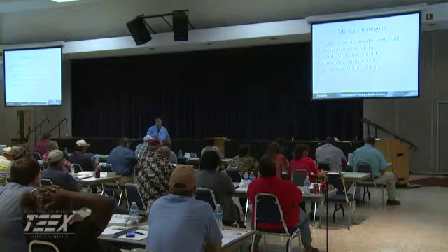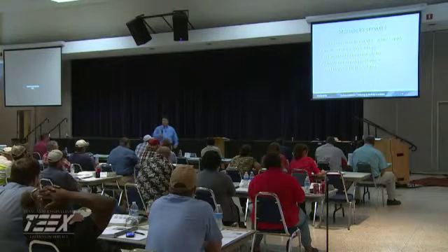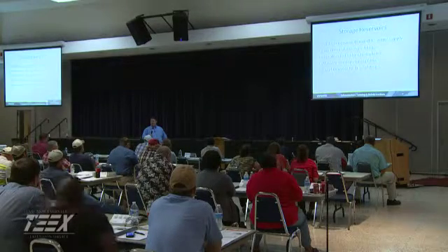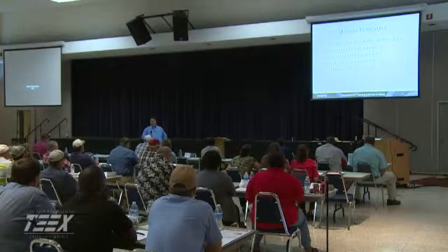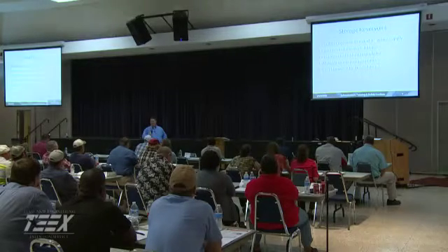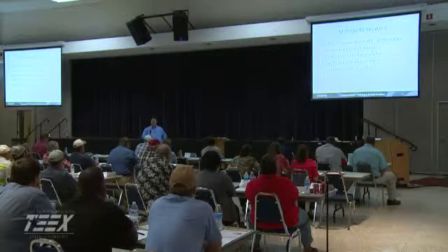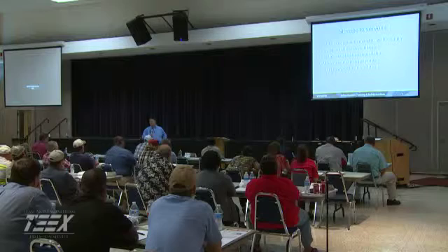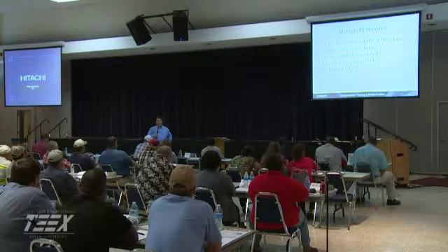Like I talked about a little bit ago, it allows you to have adequate water for firefighting, because you may not realize how much water one fire hydrant can take. If you have a large fire and you have 2, 3 fire hydrants going or more, a single 4.5-inch fire hydrant, at the right pressure, can put out 2,000 to 2,500 gallons a minute. And if you've got 2 fire hydrants going and you've got one 3,000 GPM well, you can take that tank down pretty quick.